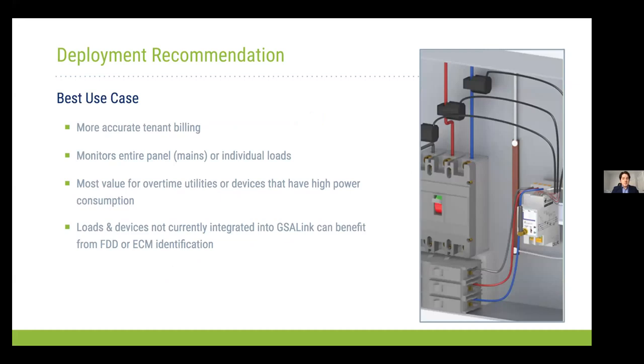What are the best use cases we've seen for this? These high accuracy CTs can be used for tenant billing, and also to monitor the entire panel of the mains or individual loads. This would not be the best option if you want to monitor 42 circuits in a single panel—not recommended, as it would take up too much space.